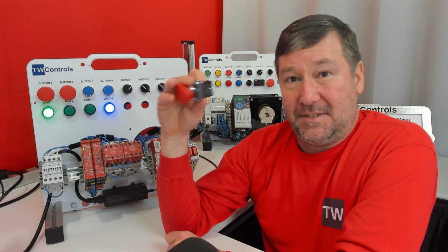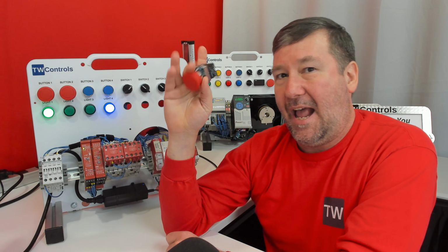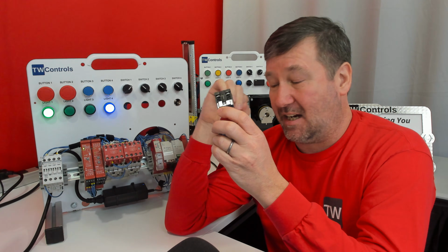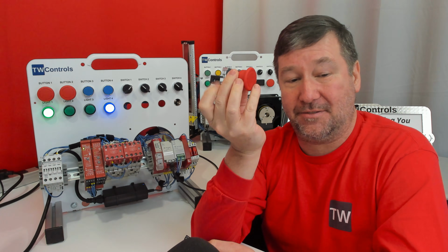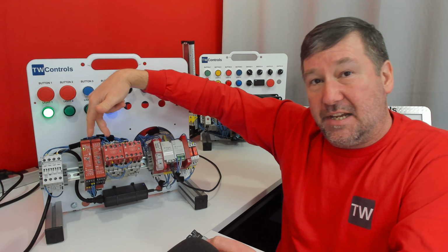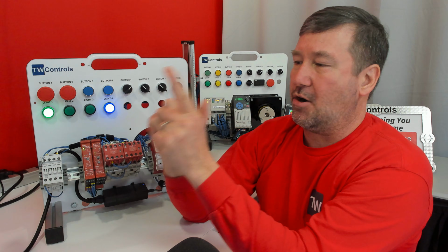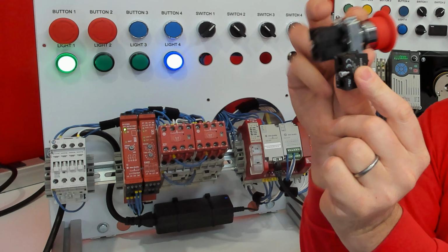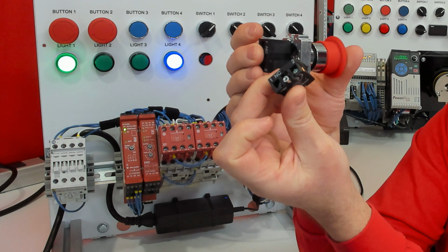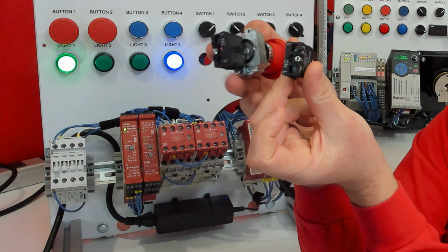Now, there's another step to this, and this one right here can really trip people up. Now that we have had one contact fail, you can almost imagine that contact's not there, and you're back to a single point failure on your system. So in addition to looking for both of those contacts, it's also monitoring, are they moving together? So in this case, if the e-stop contact is broken, it's actually physically loose now, and we press this e-stop, it only saw the one contact move and this one stayed.